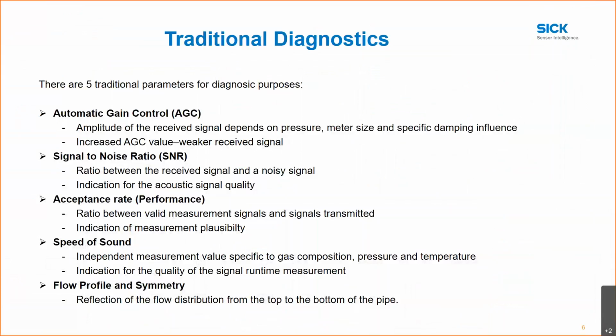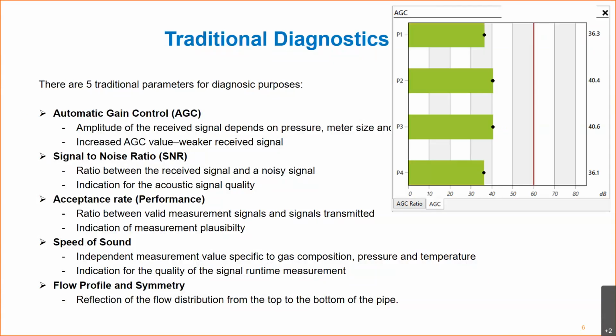The automatic gain control has to do with the signal being received, and depends on the pressure, the meter size, and any specific dampening influences like the gas composition. A higher automatic gain control value usually indicates a weaker signal. If we take a snapshot of the diagnostics we just saw on the previous page, this is your gain levels. Once these gain levels increase, it could be an indication that you have some contamination in the line, some buildup in front of the transducer, or possibly some liquids in the line.